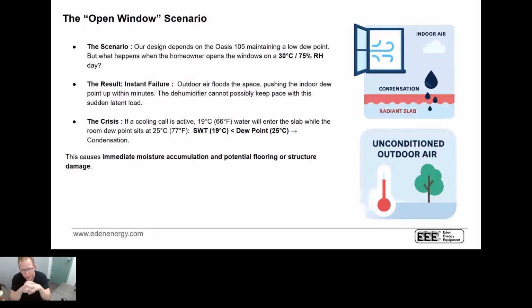So as we look at what happens, certainly decoupling the sensible and latent cooling loads is really, really important. You can do that through a dehumidifier. It comes into the open window scenario that I've already walked through. So the whole scenario is that, yes, you've maintained the space. You have not put in the dehumidifier we just talked about, but the window opens up and now you've got this challenge. Well, let's take it a step further.